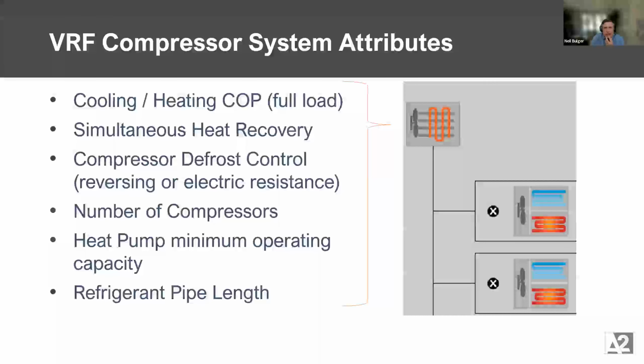But let's get into the mechanics a little bit. So now we're going into the components. What can we actually define in the components and then even represent those in the model? So at the compressor, at the outdoor unit level, we have efficiency, the heating and cooling efficiencies. We have the ability to say, is it able to do simultaneous heating and cooling? Can we move heat around the building?